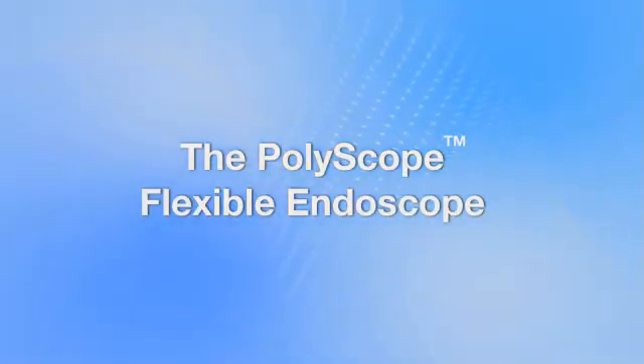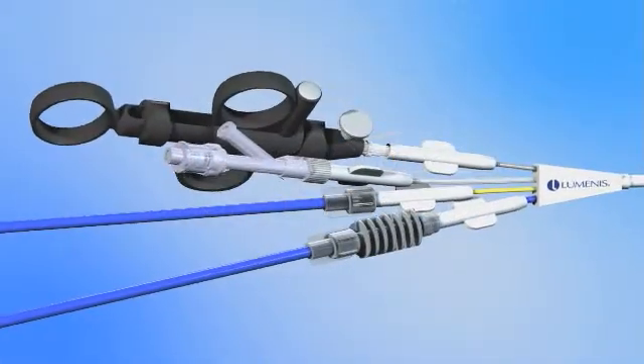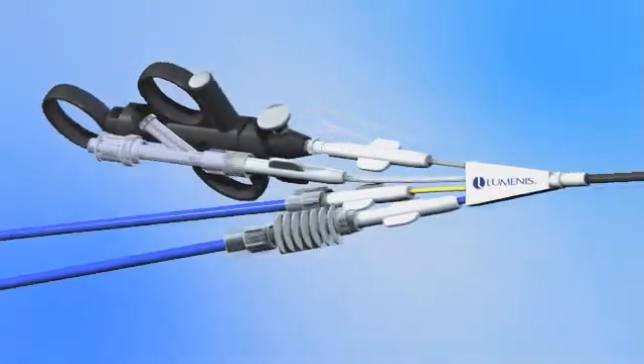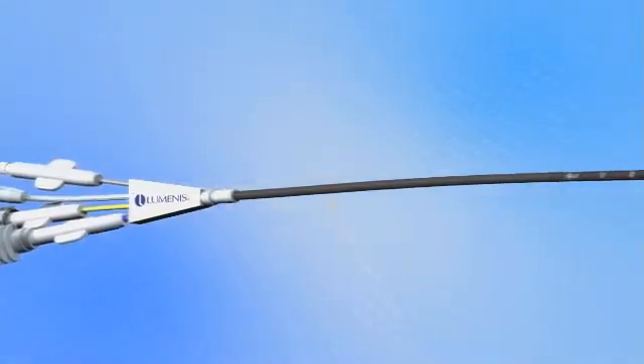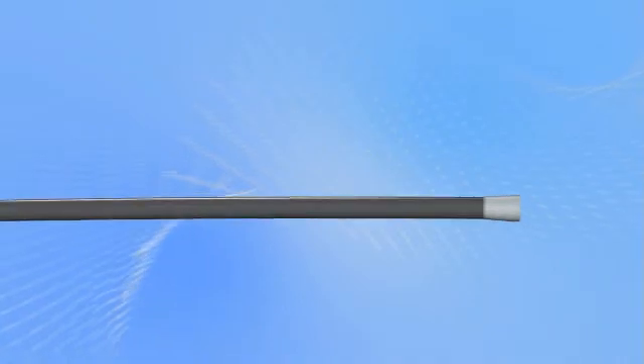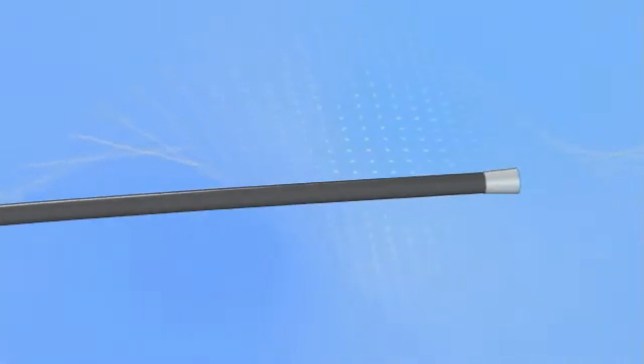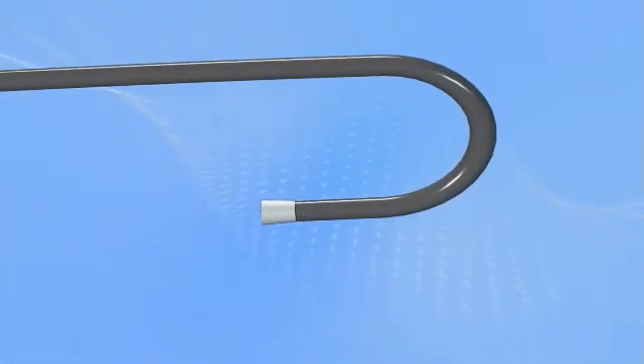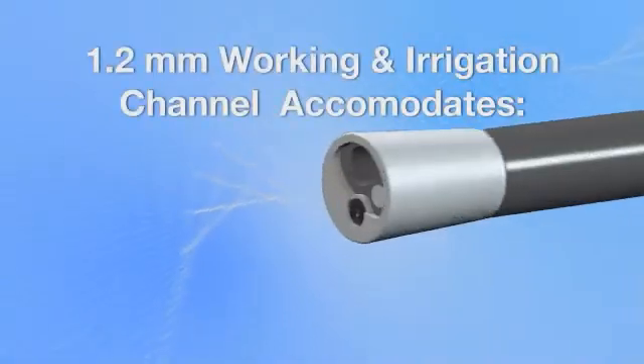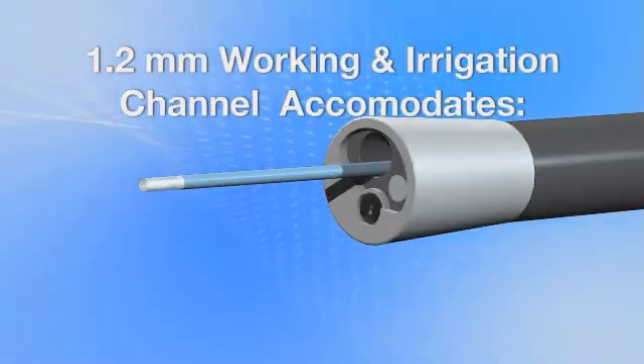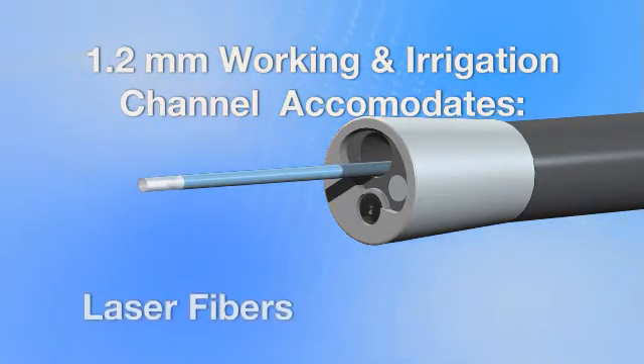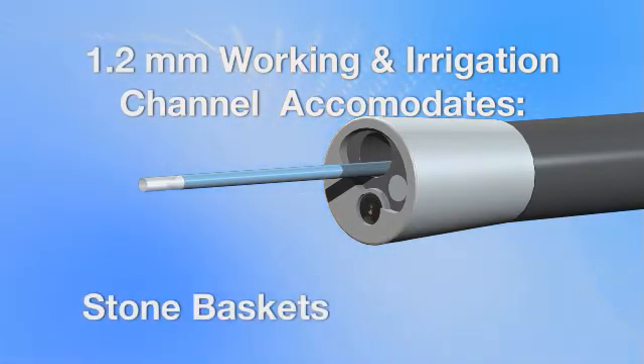The PolyScope flexible endoscope from Lumenis is a breakthrough in disposable flexible endoscopy. The PolyScope catheter body is only 8 French in diameter and delivers high-quality images through a 10,000-pixel fiber optic.